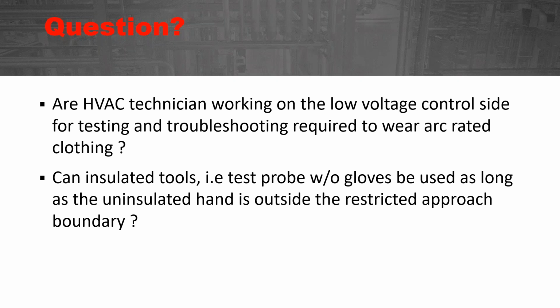All right, then the next question, can insulated tools, that is test probes without gloves, be used as long as the uninsulated hand is outside? All right, so if the hand is outside the restricted approach boundary, well, you're going to have really long probes on the test instrument, because otherwise at anything 208 volt or over, 150 volt up to about 750 volt, the restricted approach boundary is 12 inches. So if the hand is within 12 inches, then shock protection is required, therefore rubber gloves with leather protectors.